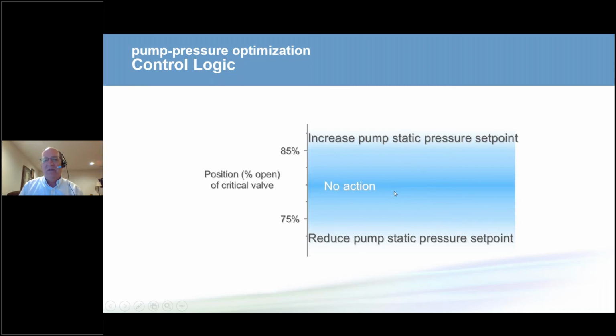And what we've done is only put the amount of power we need into that pump to satisfy the worst case load. Another thing this does is, in the past, we used to have to guess where to put the differential pressure sensor. Where's the most remote air handler? Now we can actually have the DP sensor in the plant and reset it on the critical valve position. We don't have to guess, because in the morning, the critical zone and valve will be on the east side of the building. In the afternoon, it will be on the west side of the building. The automation system technology changes and optimizes the system for us at every point during the day.